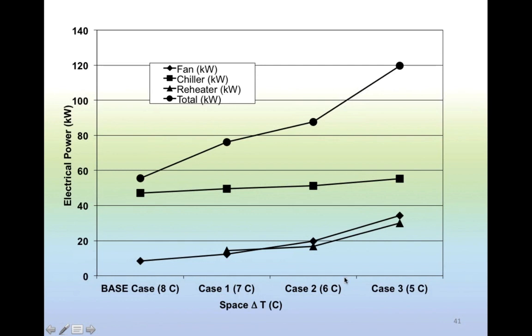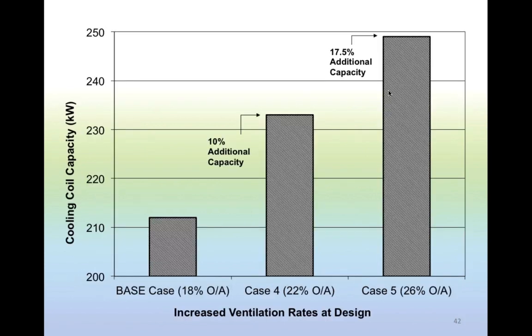Space delta T, well, you've got the different cases, 8 degrees Celsius, 7 degrees Celsius, 6 and 5 degrees, and here are all the energy consumption increases that we're talking about. And you can see here, the total energy consumption can be quite drastically increased if we move away from, say, a base case of 8 degrees to a lower delta T of 5 degrees Celsius. As I said, as one last consideration in that particular study, we looked at what happens if we were to increase the outside air percentage.